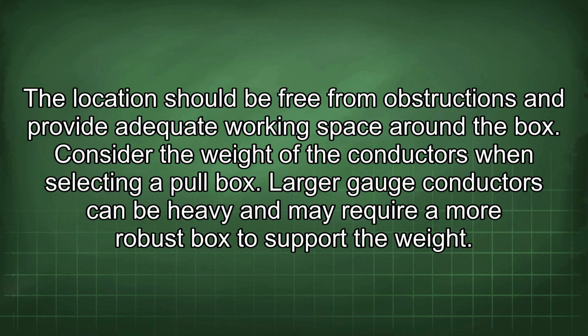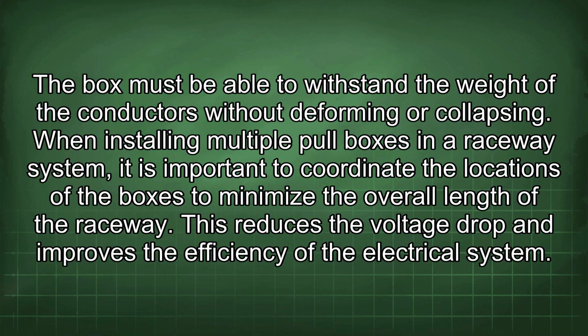Consider the weight of the conductors when selecting a pull box. Larger gauge conductors can be heavy and may require a more robust box to support the weight. The box must be able to withstand the weight of the conductors without deforming or collapsing. When installing multiple pull boxes in a raceway system, it is important to coordinate the locations of the boxes to minimize the overall length of the raceway. This reduces the voltage drop and improves the efficiency of the electrical system.